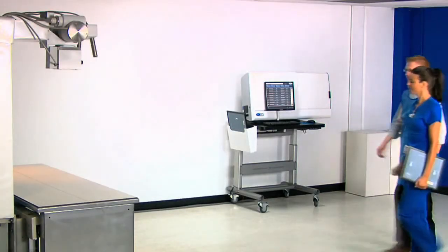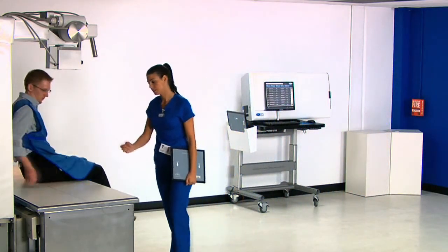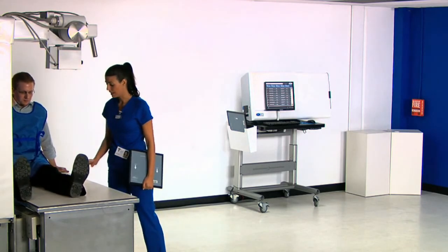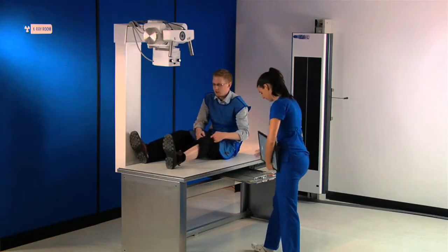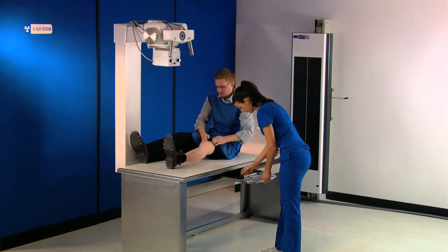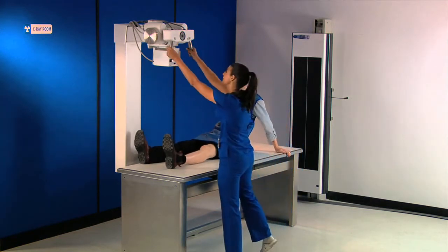The ICR 3600 is a computed radiography machine, ideal for general radiology. The system incorporates a true flat scan path technology. This technology ensures the phosphor plate never leaves the cassette to avoid any plate handling, damage, or wear during the scan process.